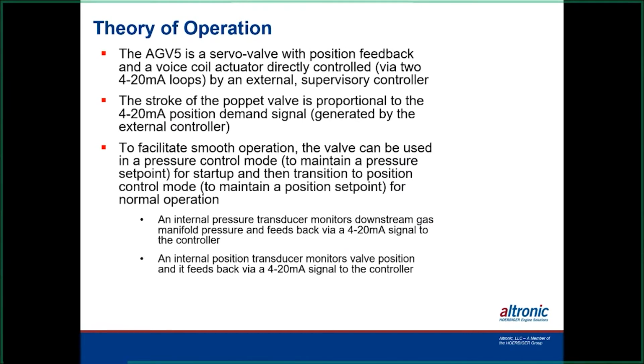Again, it runs off of a 4-20 from some internal device, either a PLC, or we have a Gov Plus that I'm going to mention a little bit here at the end that will also control this valve if you don't have an outside source of a supervisory controller. Again, it's a poppet valve with a signal that comes back, which you can use to let you know the valve is actually operating. So it's a very nice feature to use.